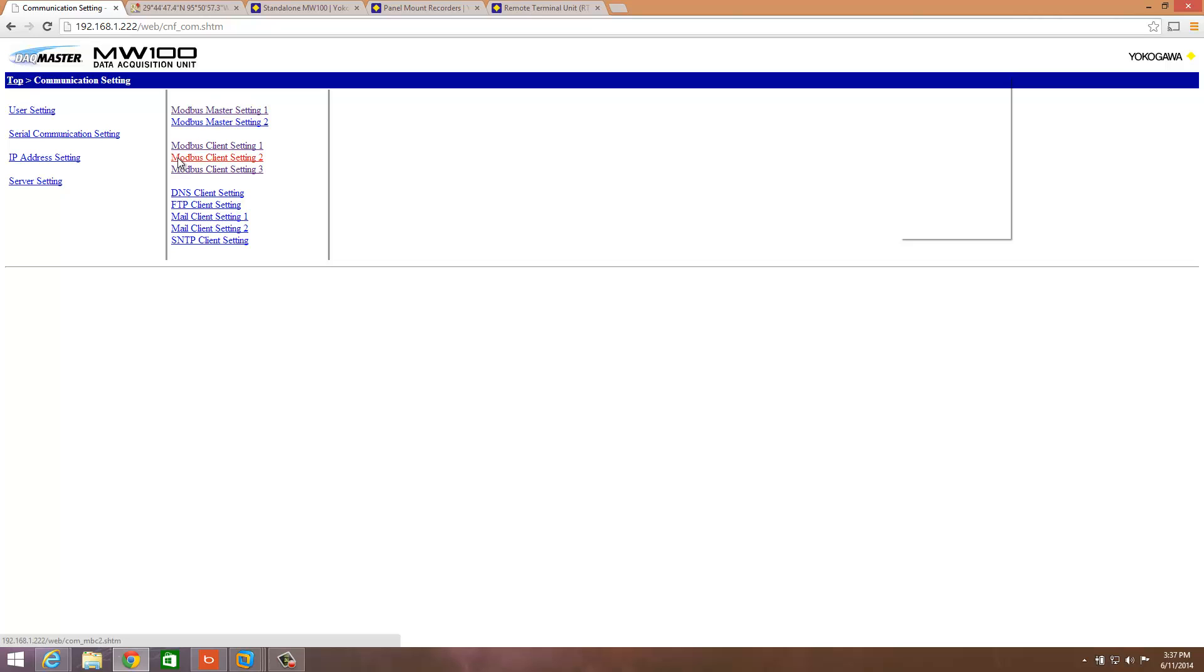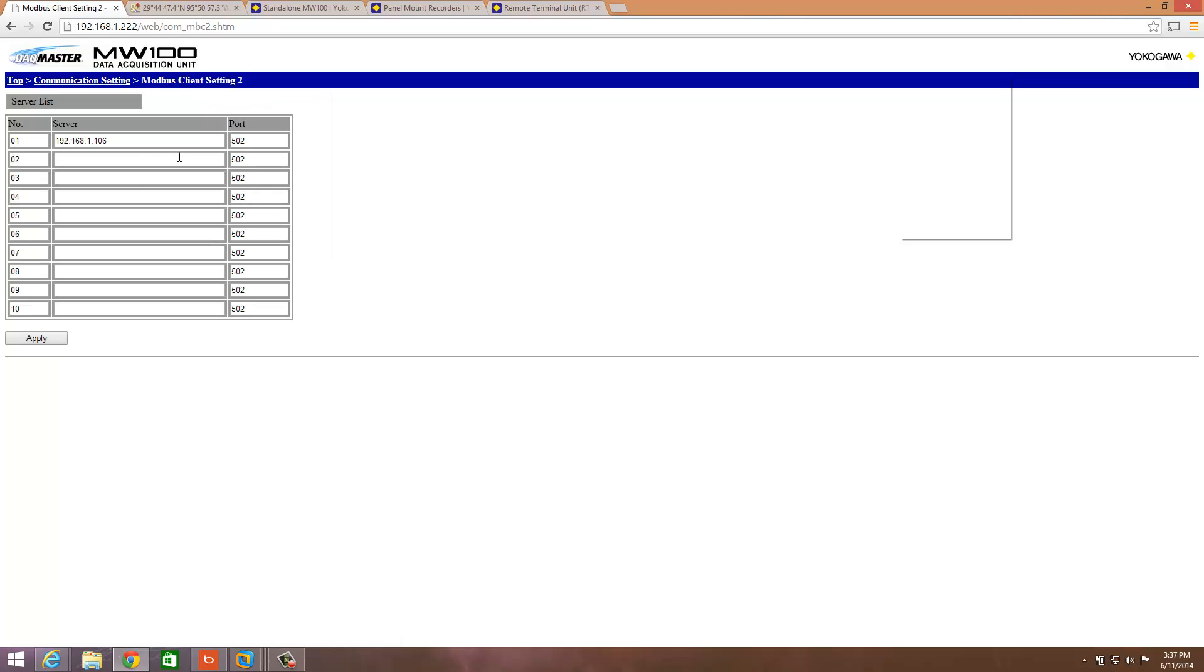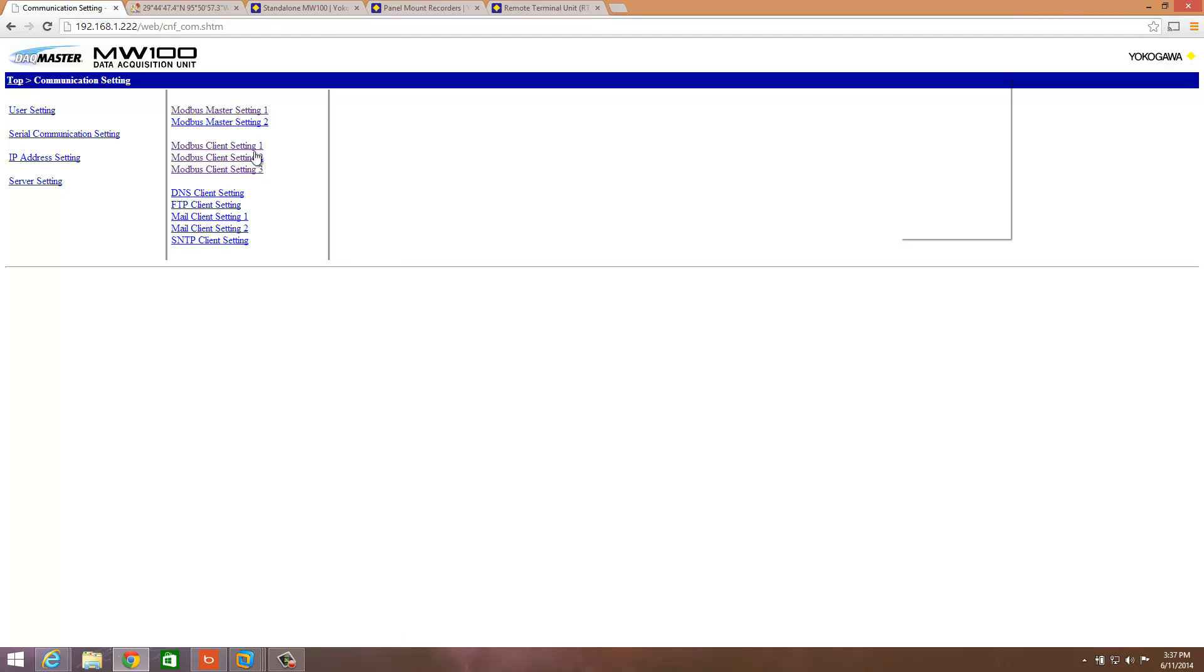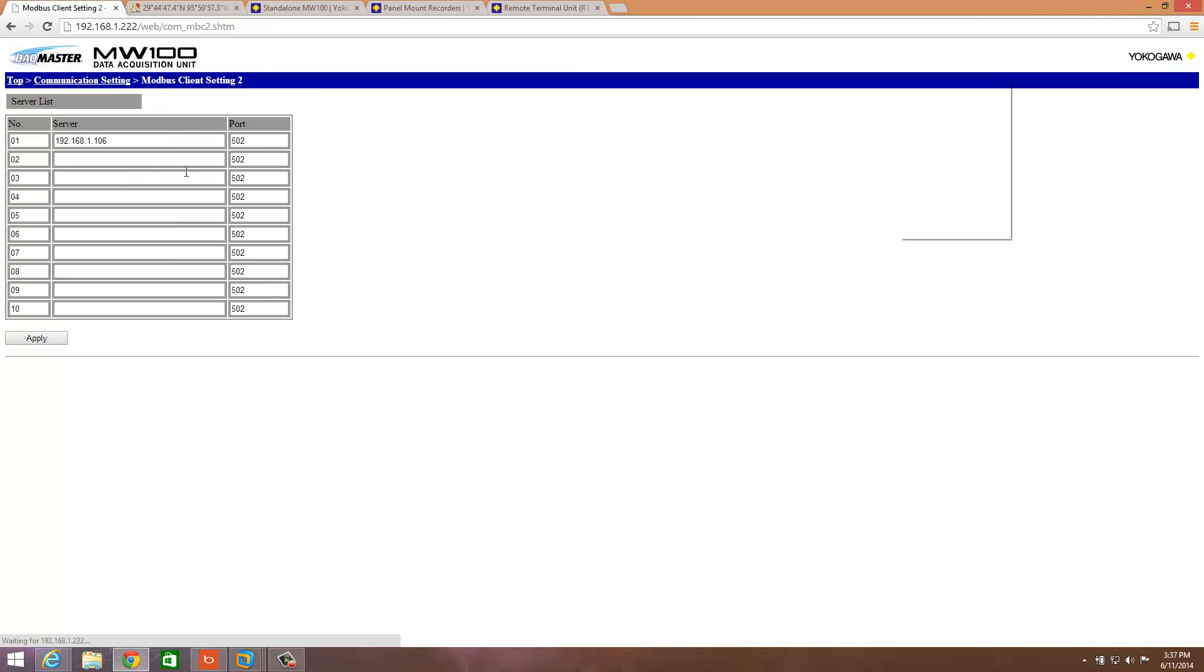The next place we're going to go is the Modbus Client Number 2. Under this, you're going to put in the IP address of the CloudGate. Port 502 is standard for Modbus, so you can leave that as standard. And then the next place we're going to go here is the Modbus Client Setting Number 3. Of course, every time you do settings, make sure you hit Apply at the bottom.